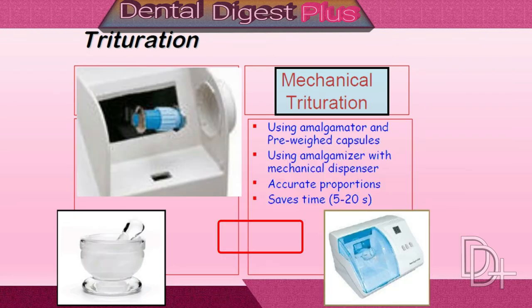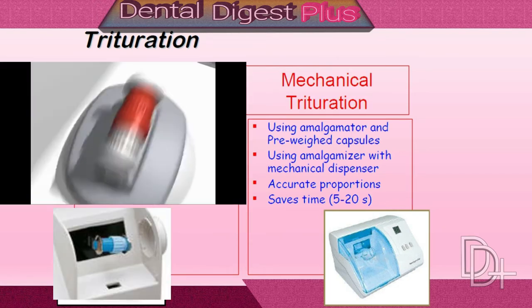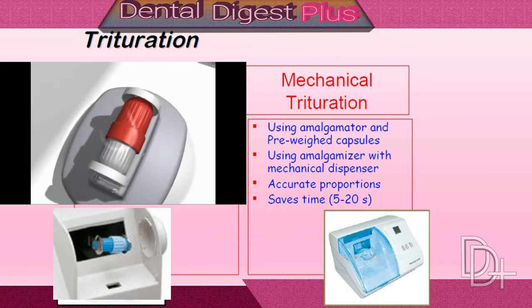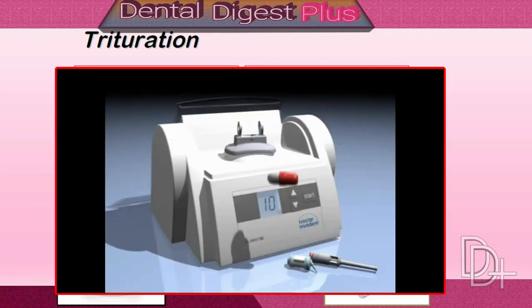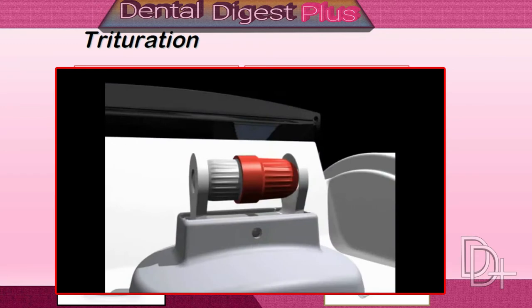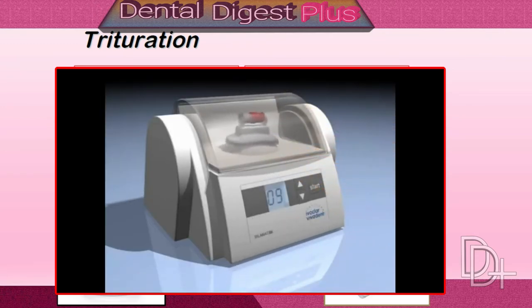The mixing arm carrying a capsule can move back and forth in a straight line, or back and forth in a figure of eight, or in centrifugal movements. When the capsule has been secured in the machine and it is turned on, the arms holding the capsule oscillate at high speed — this is how trituration is accomplished.